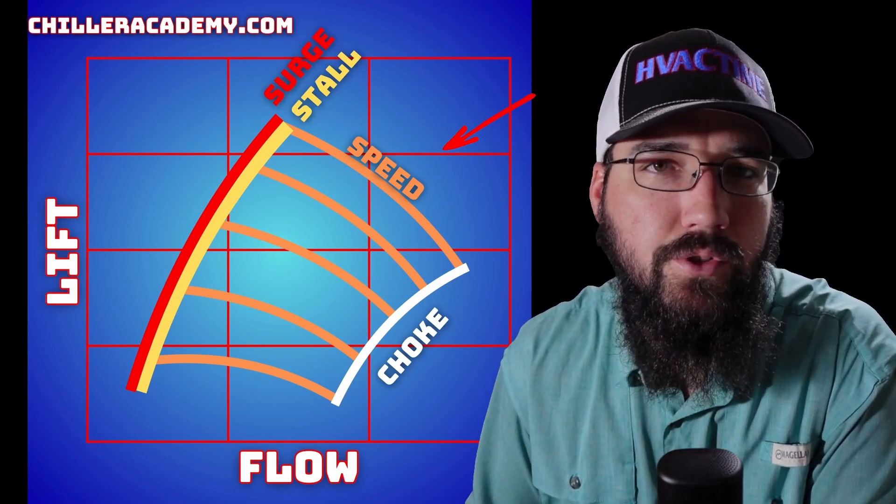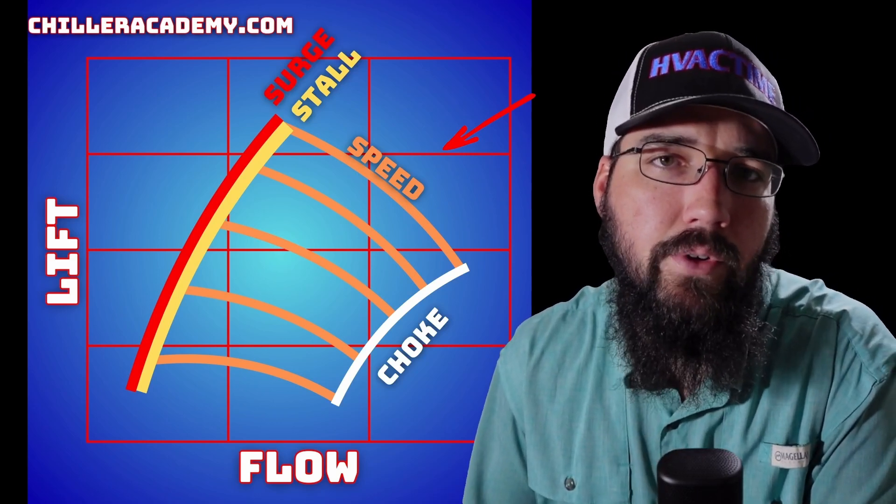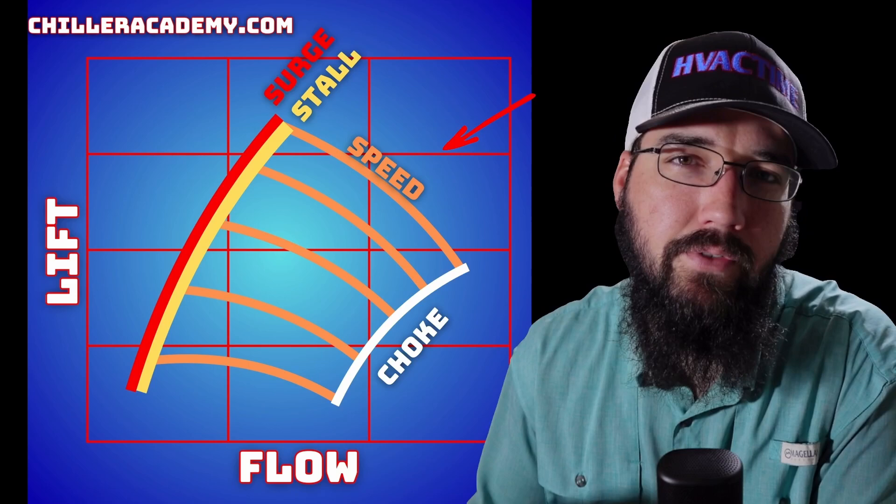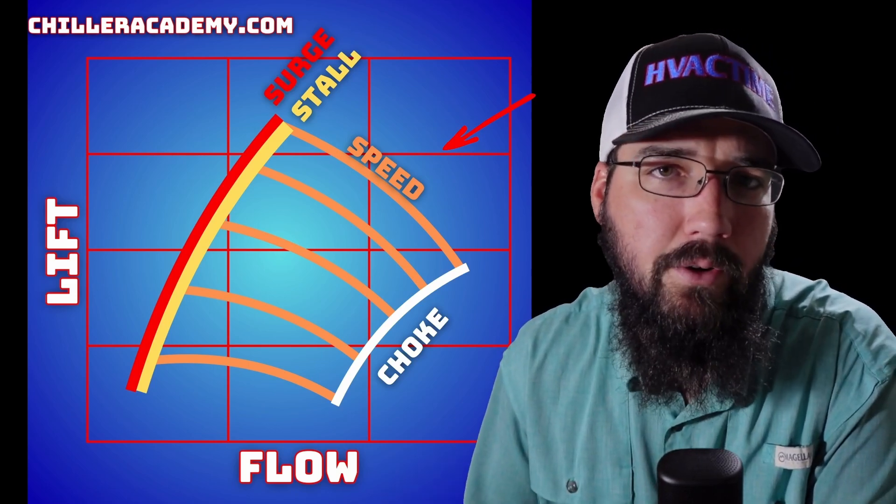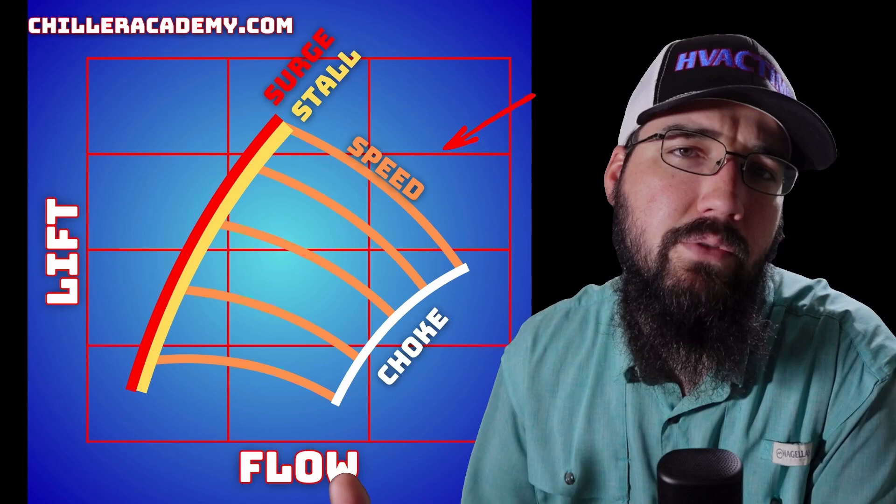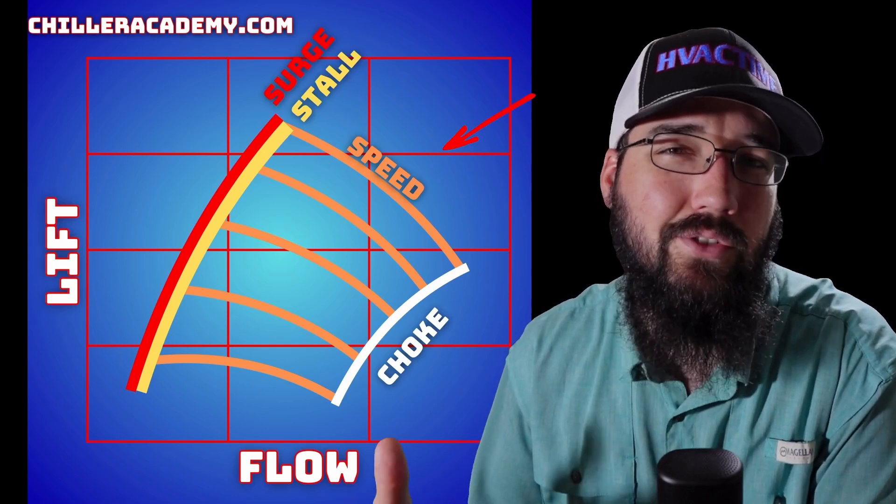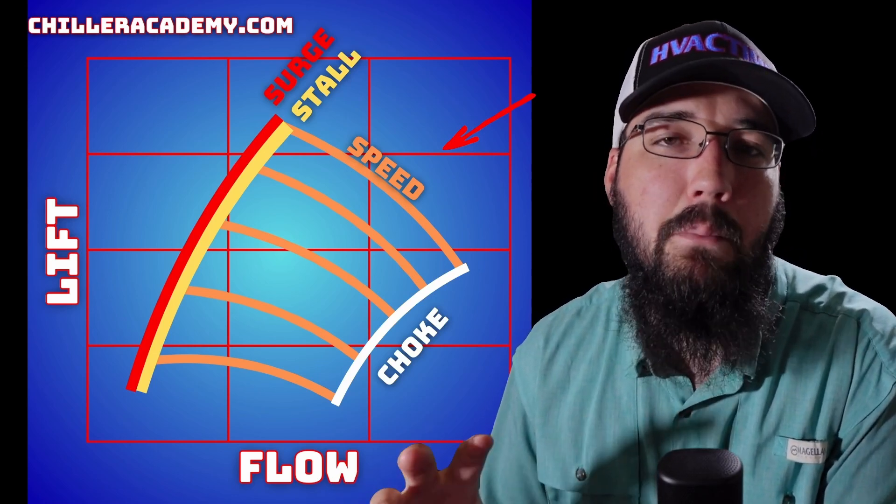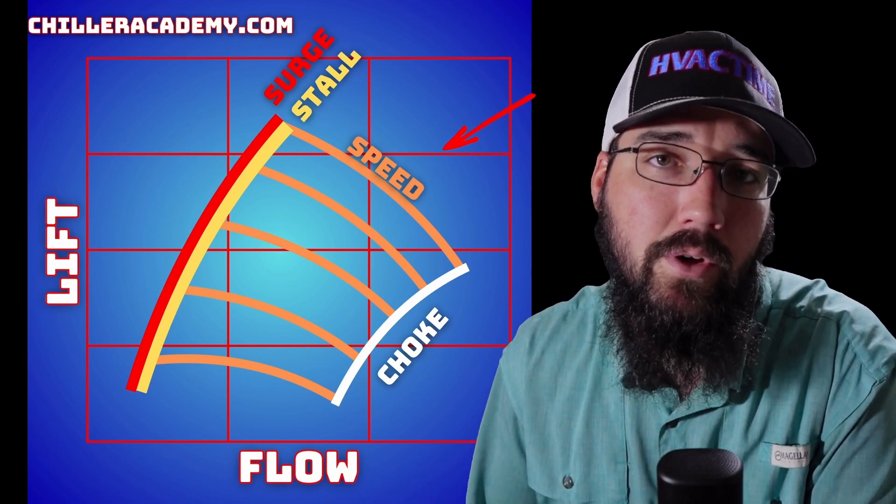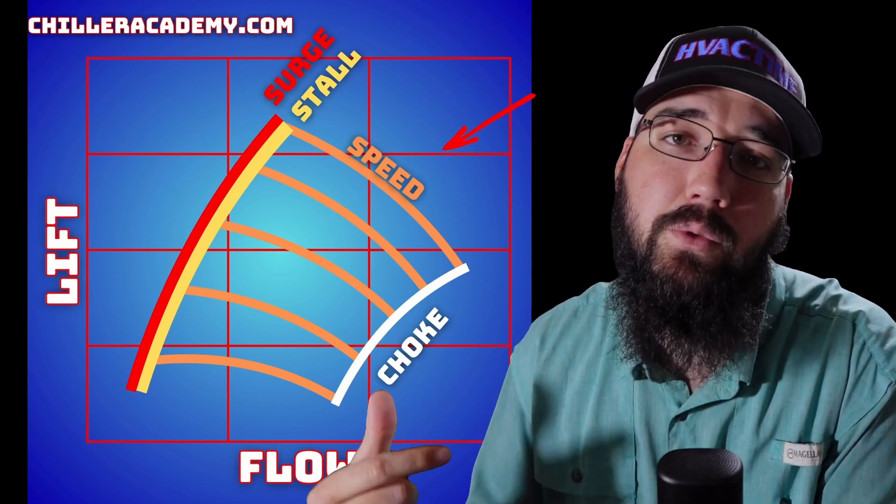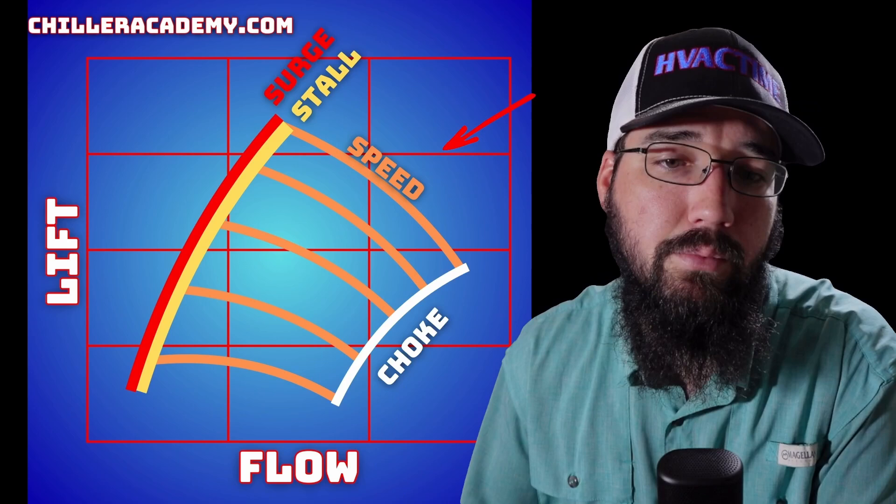This is a centrifugal surge graph, and similar to a centrifugal water pump flow graph where we can see the optimum flow and horsepower requirements, every centrifugal compressor also has a surge graph. It's how we can monitor where the surge point is, or where we are in relation to that point based on our lift—the difference between condenser pressure and evaporator pressure.